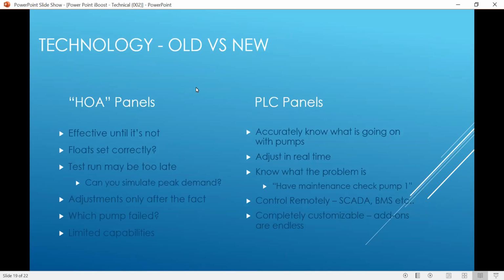On technology, HOA versus PLC, obviously, we kind of went into that. Your adjustments are much easier. What pump failed gives you an idea. And like I said, if you have a remote control access through SCADA or BMS, the PLC gives you the ability to do that. And we feel like that's a leg up from the standard HOA system.